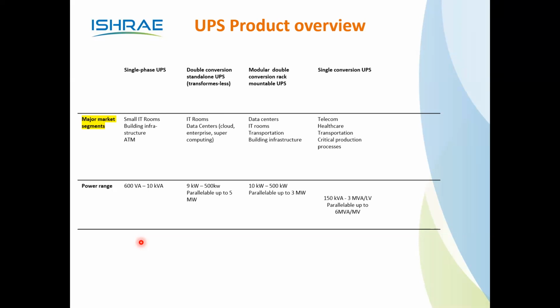Now, how does the double conversion happen? It happens from grid supply to UPS: it converts from AC to DC and DC to AC. That's the main reason it's called double conversion. It's purely meant for critical applications, and it's totally isolated. The double conversion UPS systems available in the market are from 10 kVA and above, and can go up to 5 megawatt.